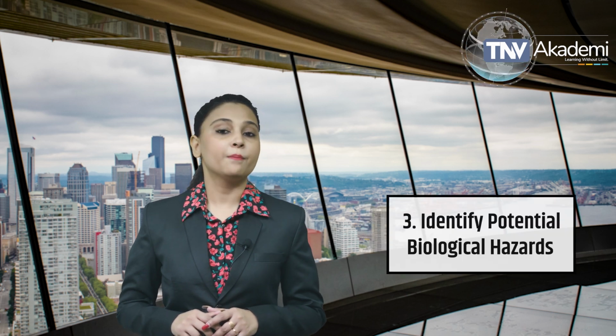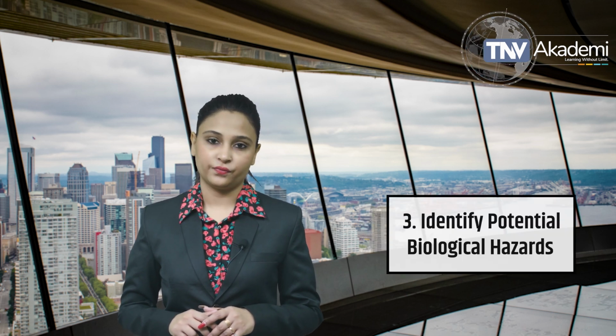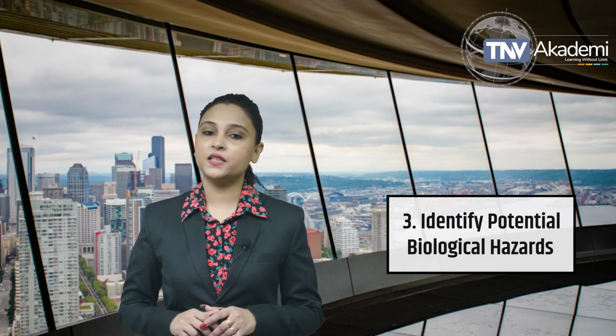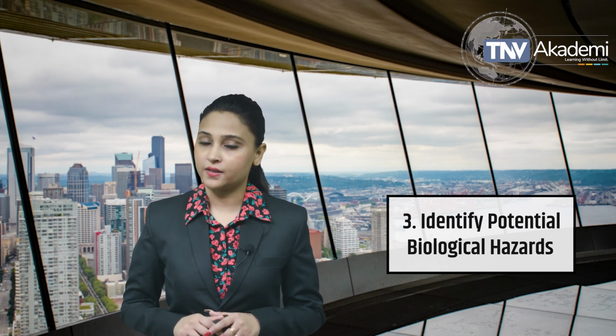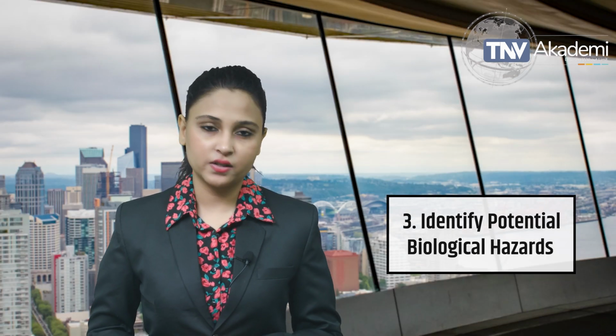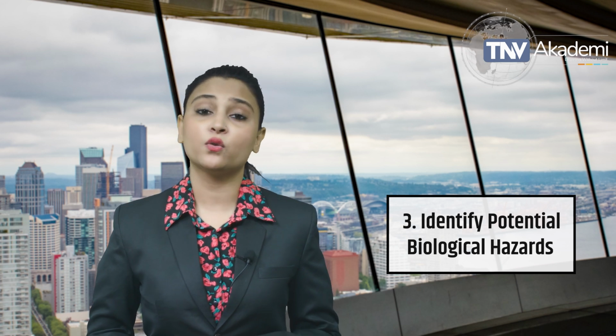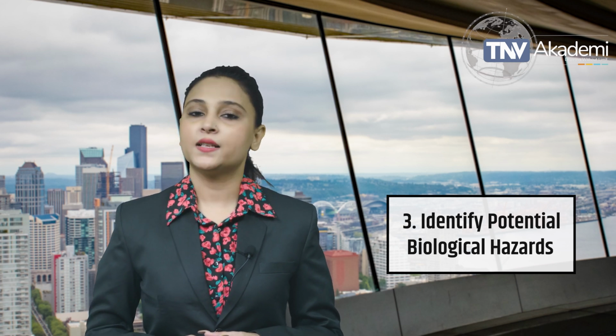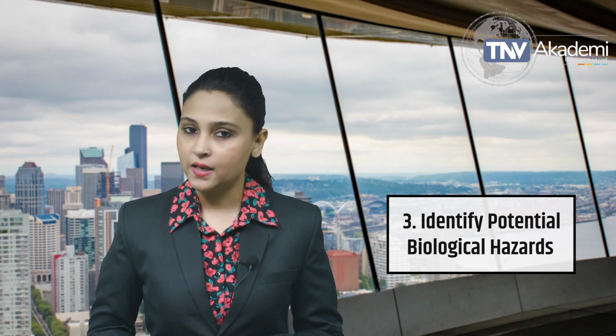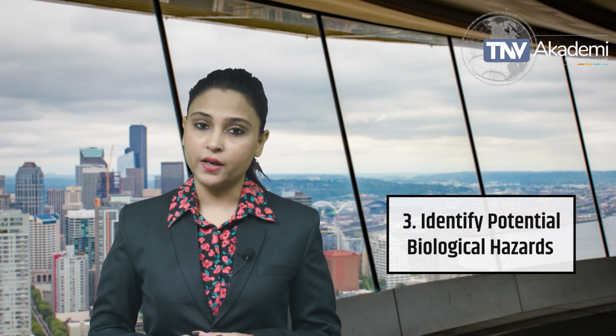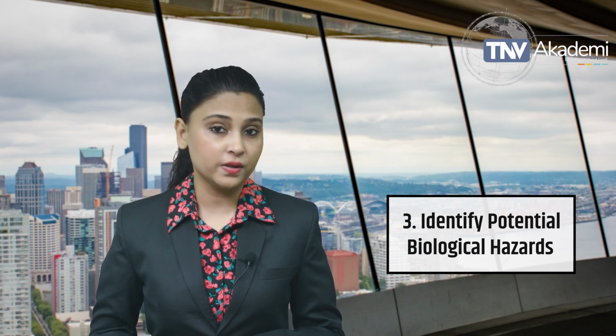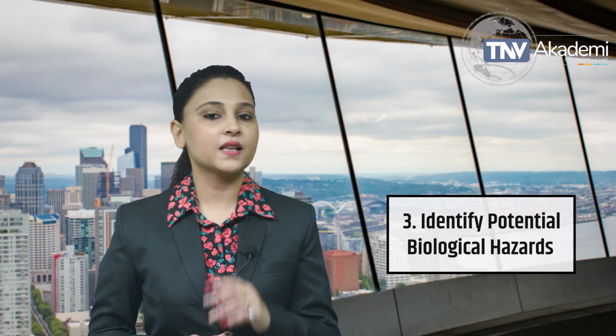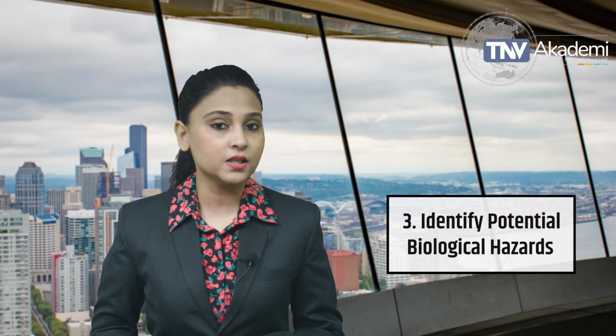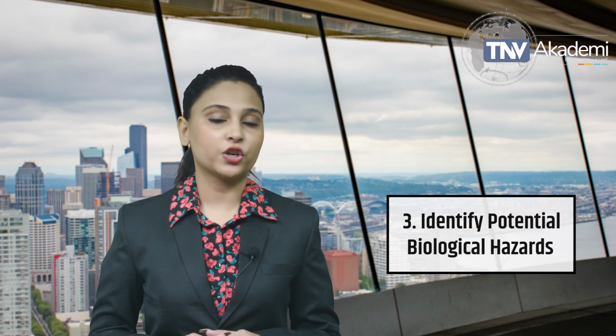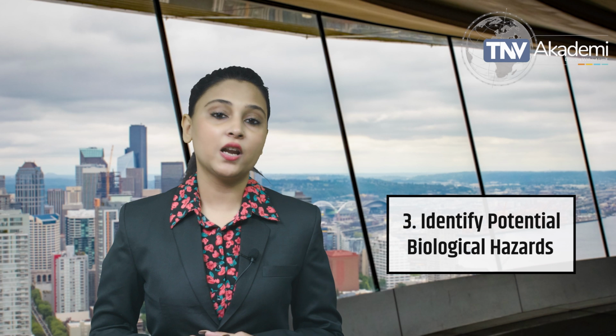Identify potential biological hazards. The next step is to identify potential biological hazards. Using ISO 10993-1, determine which biological endpoints such as cytotoxicity, sensitization, or genotoxicity need to be assessed. This hazard identification process considers the materials, manufacturing methods, and sterilization techniques used.